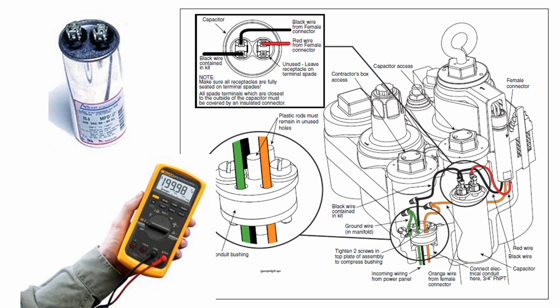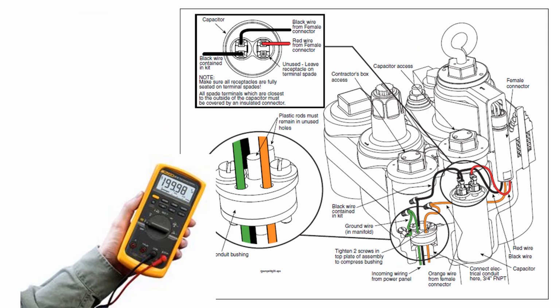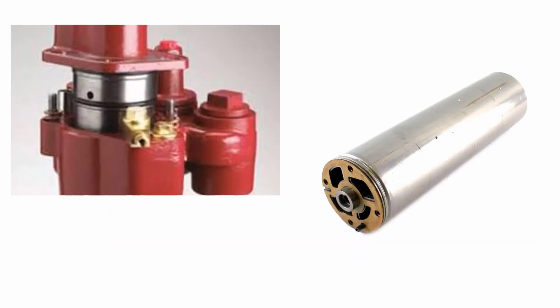Measure the resistance from the contractor's box to the UMP. If the resistance is infinite, pull the motor. Test the pigtail and motor resistance. If the wiring is good, the pump shaft or bearings could be bad, causing the UMP not to turn. With the UMP disconnected from the STP, check to see that the shaft spins freely.